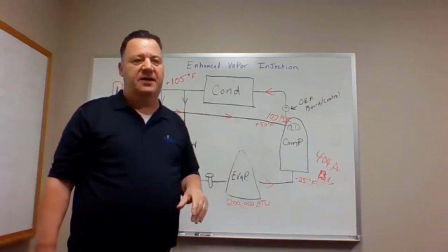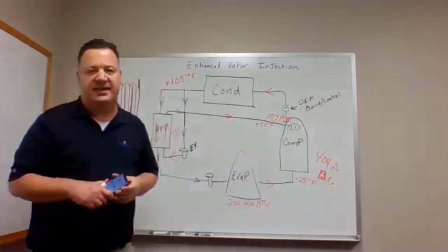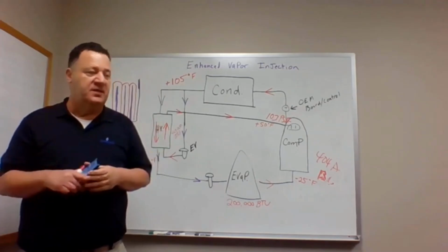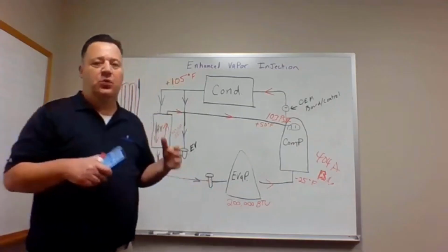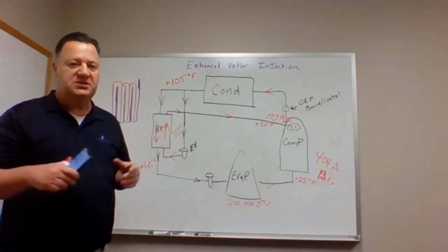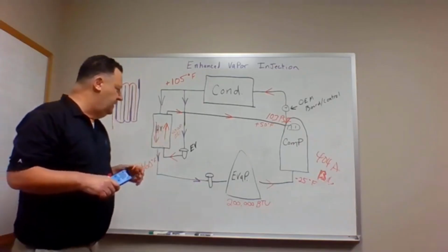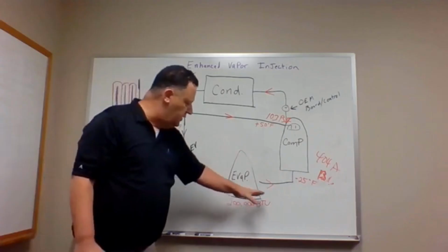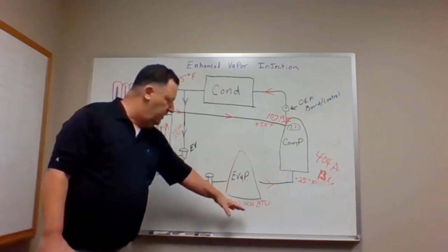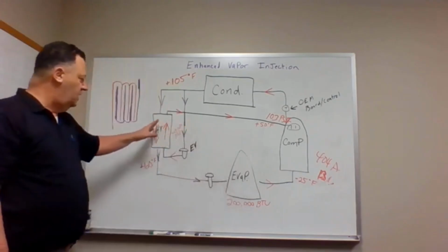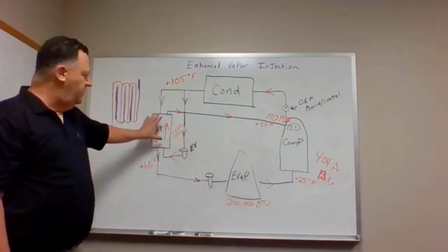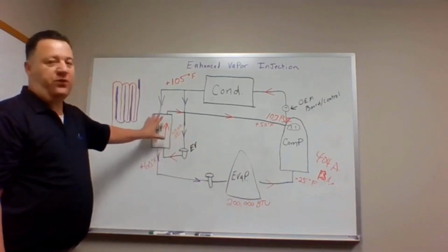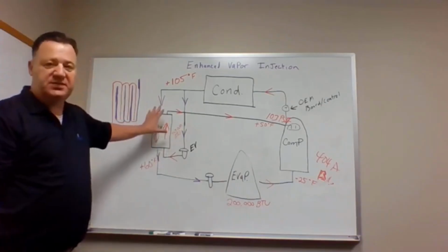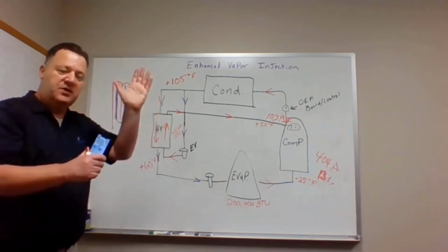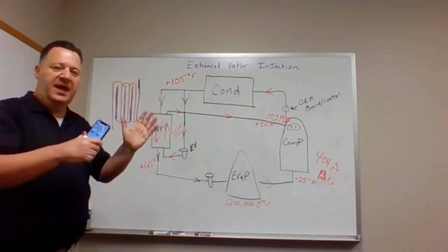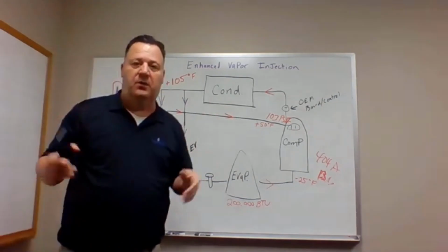This is the kind of equipment you'll see in our X-Line condensers, by the way. This is the kind of thing that's in those. You can get liquid or vapor injection with the braze plate heat exchanger. Now we have the digital compressor in there too, which is really cool. Okay, so hypothetically, if this is a 200,000 BTU unit, for example, we call it load shifting. We're actually taking part of the load outside of the compressor and moving it over here. Let's say we can get as much as 40,000 BTUs just by using this braze plate heat exchanger, just by those two refrigerants, liquid and vapor, passing each other and using basic physics, hot going to cold, okay?